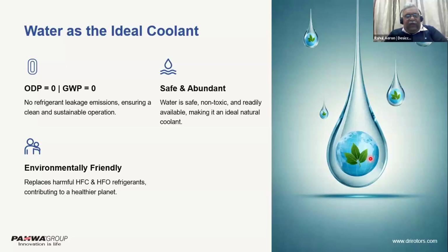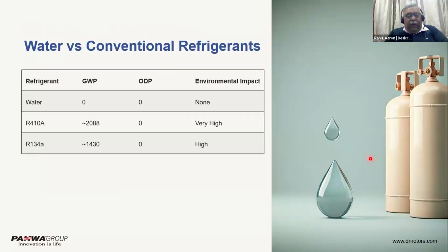Now, why water? Water, because it has no ozone depletion potential. It has no global warming potential. It is safe. It is abundantly available, and it is eco-friendly, totally eco-friendly. So that is why any evaporative cooling system is always a net zero carbon system. Just to give you some GWP and ODP values of other refrigerants, you see R410 has a GWP of 2088, which is very high, and R134A, which we use in our package units and windows and splits, is almost 1430.